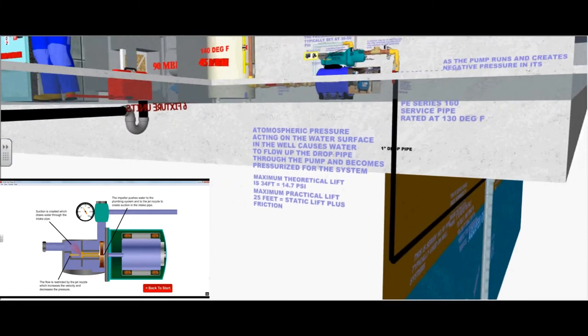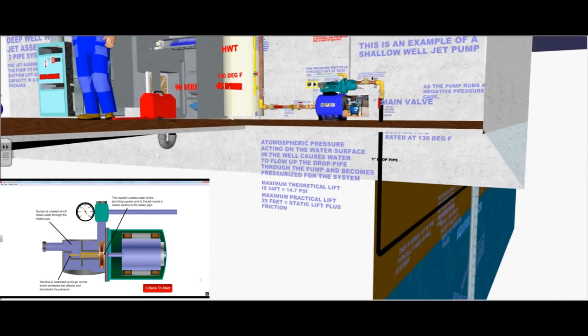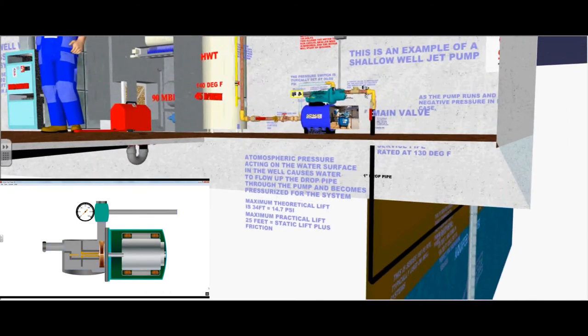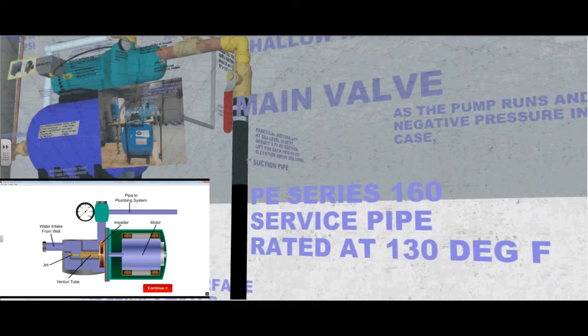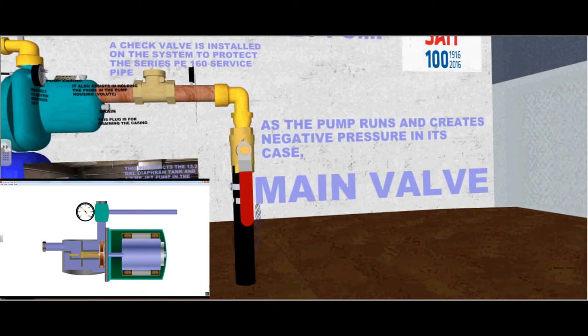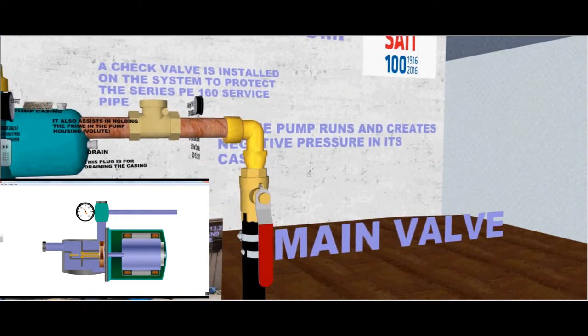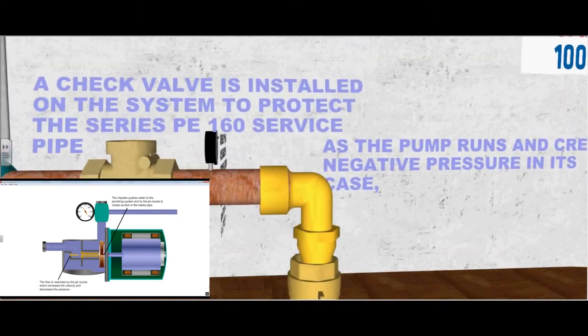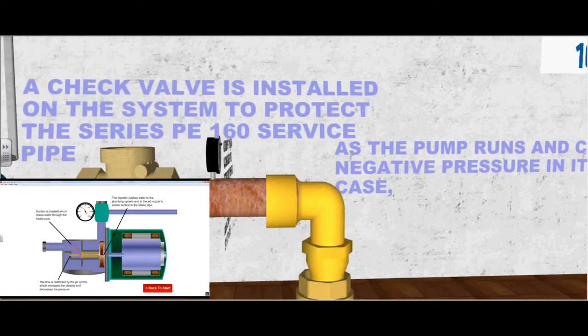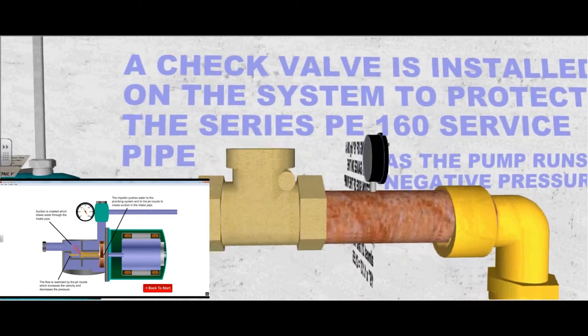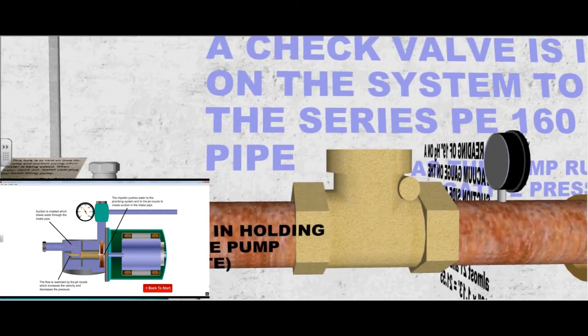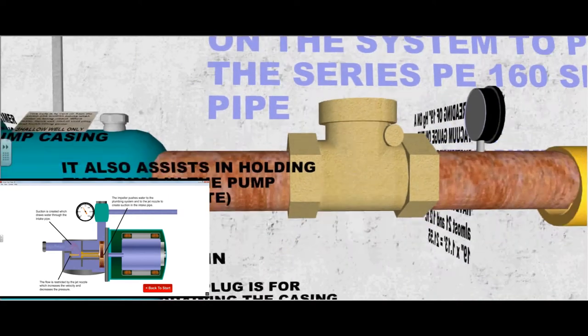There is an example of maximum and practical lift. Here the polyethylene service pipe is double clamped to the main valve. A check valve is installed on the system to protect the service pipe from weakening, especially the clamp. It also assists in holding the prime in the pump housing or the volute.